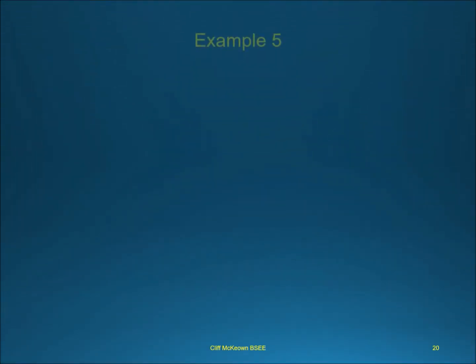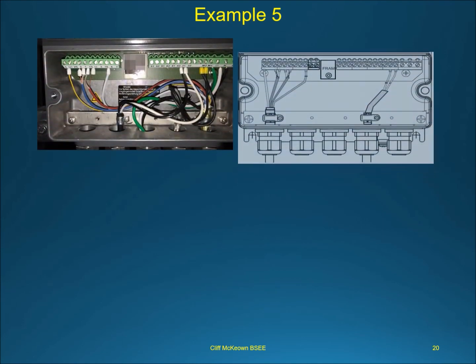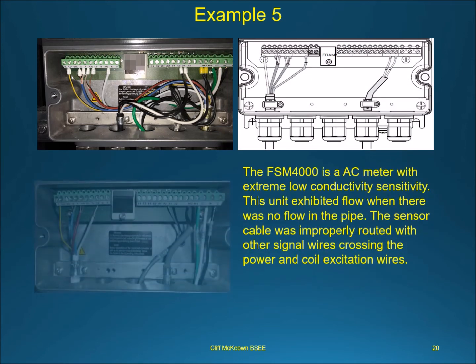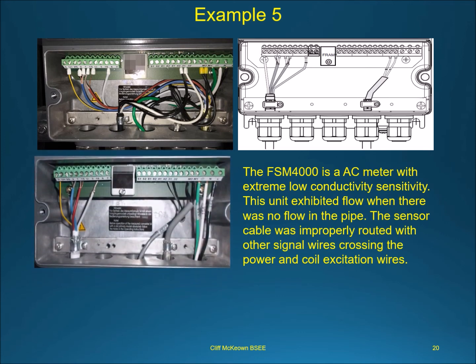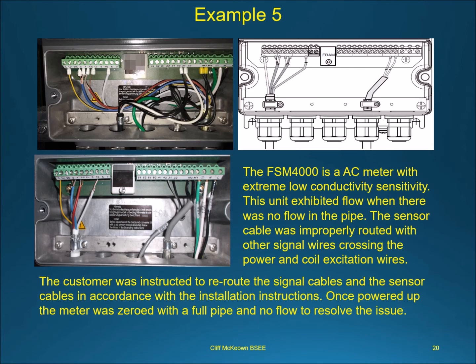The FSM 4000 is an AC meter with extreme low conductivity sensitivity. This unit exhibited flow when there was no flow in the pipe. The sensor cable was improperly routed with other signal wires crossing the power and coil excitation wires. The customer was instructed to reroute the signal cables and sensor cables in accordance with the installation instructions. Once powered up, the meter was zeroed with a full pipe and no flow to resolve the issue.